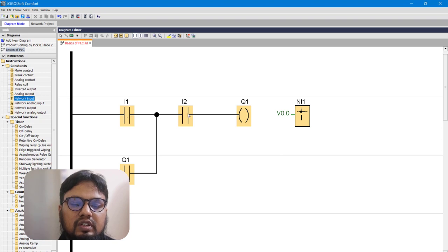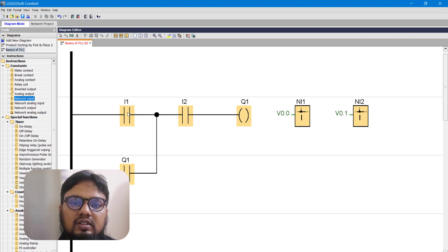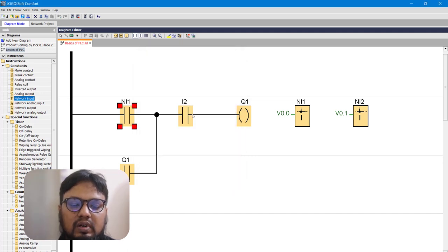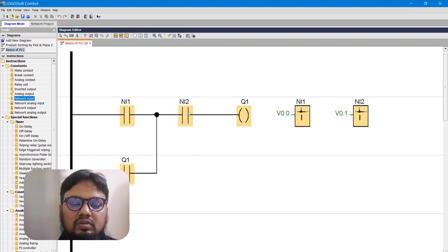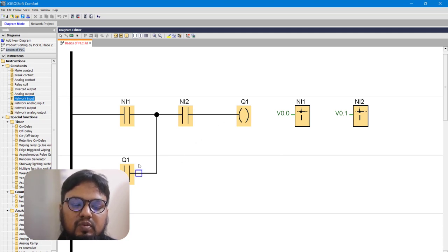We have two network inputs, so we bring in two network input blocks. The first one is V0.0 (that is 00) and the second is V0.1. The start switch is NI1 (network input 1) and the stop switch is NI2. So NI1 and NI2 are our digital inputs, and Q1 is our digital output — the conveyor belt. The program is almost complete.